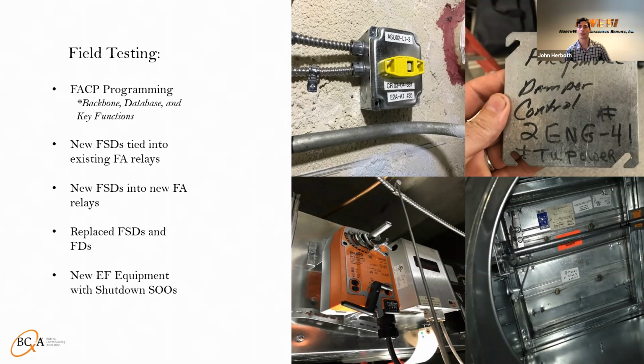Let's see, I got a question coming in here. Did your commissioning of a fire life and safety system utilize only the ANSI approved process containing NFPA 3 and NFPA 4, integrated testing of fire protection? So I've gone through and done NFPA 3 and 4, but in this circumstance, on this project, no, we weren't using that as the baseline. But those processes are standardized to help you go through and do this type of stuff. So I've definitely used that as sort of my baseline, sort of like your engineering degree, use that as your baseline. But I didn't go step by step using that as my backbone, basically.